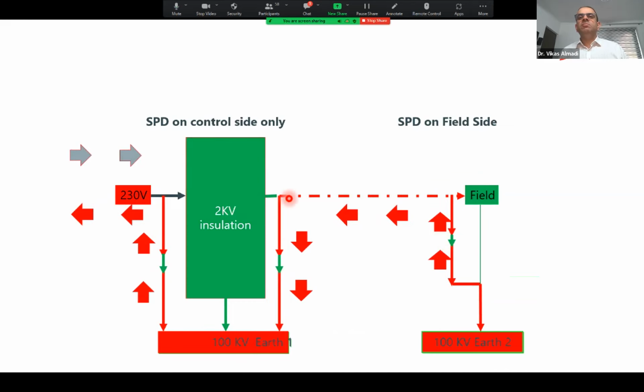So since this portion of the circuit will still be carrying the lightning, there is a possibility of surges, which can still be protected by surge protection devices. Here you see this kind of isolation or bypassing is achieved by using these switches, which are nothing but the SPDs. So SPD bypass this lightning current. Lightning current is anyway going to flow. It should not flow through our equipment or our devices, our sensors. It should bypass them and pass through the SPDs.